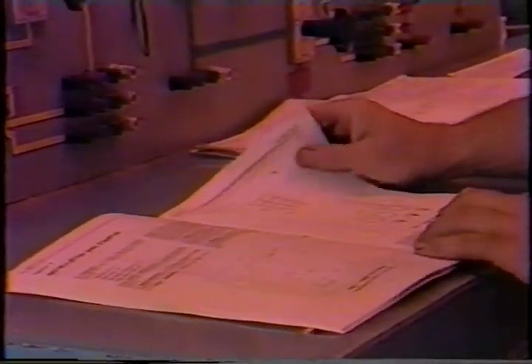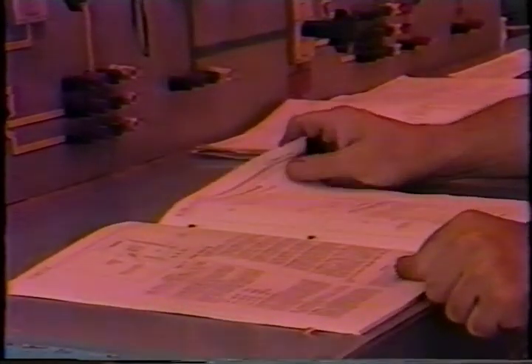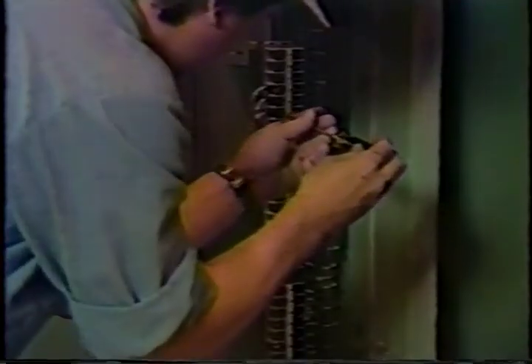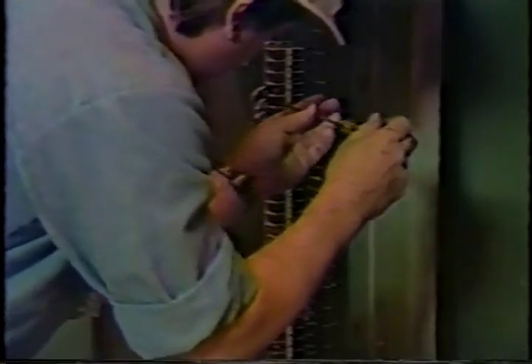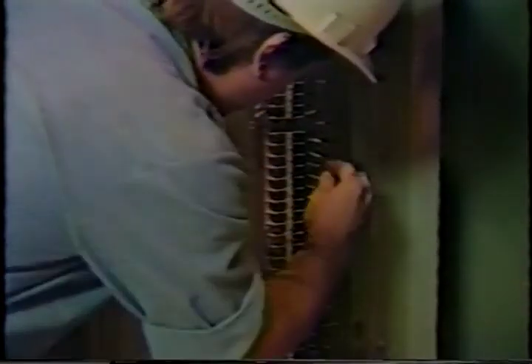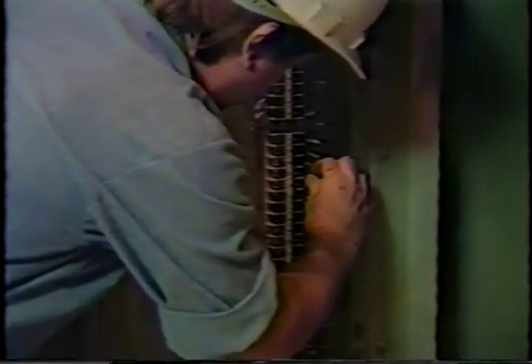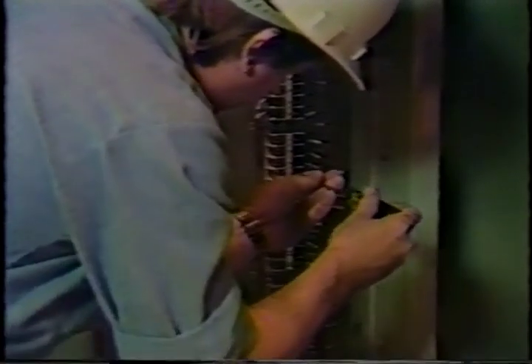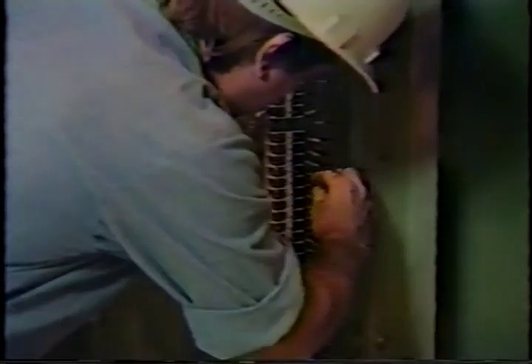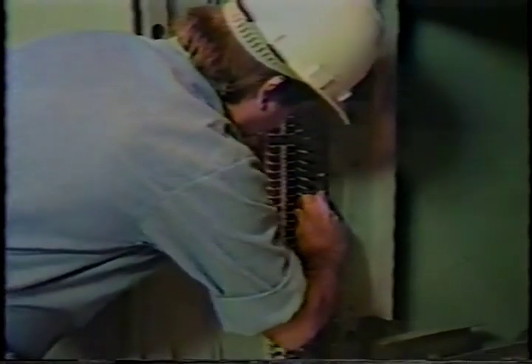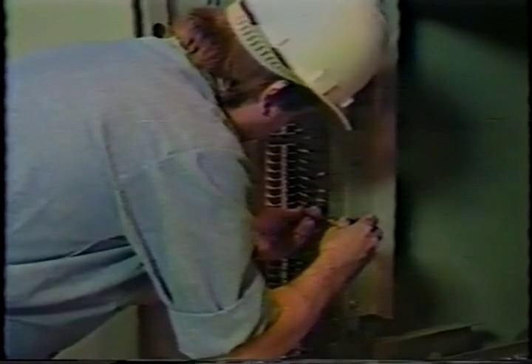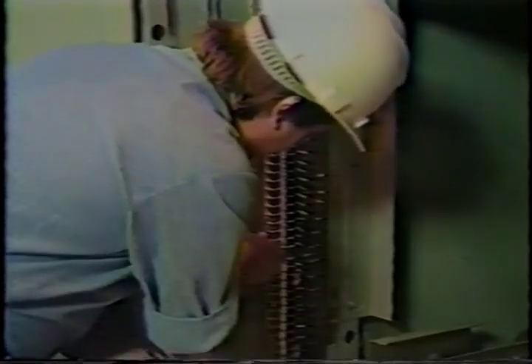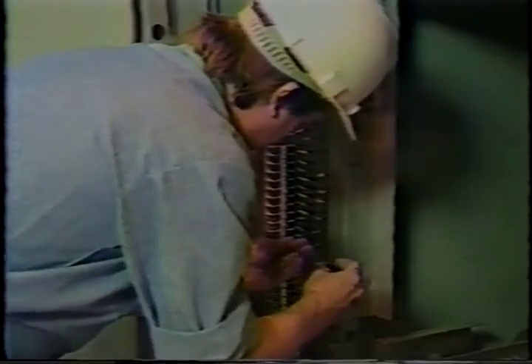Instruments, relays, and other panel-mounted devices should be maintained according to the specific instructions supplied for each device. Check all secondary wiring connections for tightness, including those at the current and potential transformers and at the terminal blocks where circuits leave the switchgear. Make sure that all secondary wiring connections are properly connected to the switchgear ground bus where so indicated.